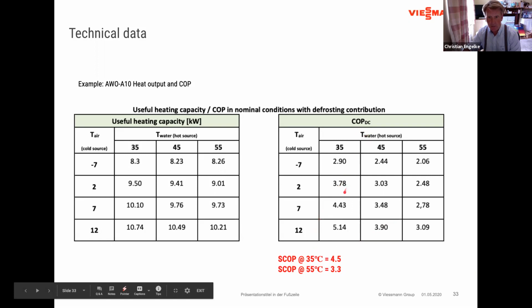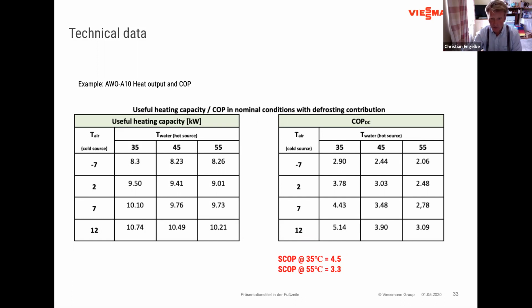As I said, COP is the measured efficiency from the manufacturer. The SCOP is the seasonal efficiency. So this assumes the seasonal effects from winter to autumn and spring and summer operations, and averages the efficiency across the year. Running the heat pump at 35 degrees, the SCOP is 4.5. Running the air source heat pump system at 55 degrees on the coldest day of the year, obviously with weather compensated controls, the seasonal efficiency will drop down to 3.3. So they're all good values, but again, it's important to consider this, and these values are all available from 35 to 55 degrees on the MCS database for every heat pump model from all manufacturers who are listed on the MCS database. So just as a reminder for this one.